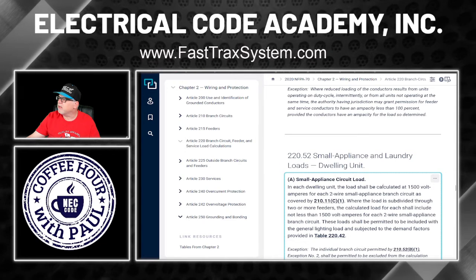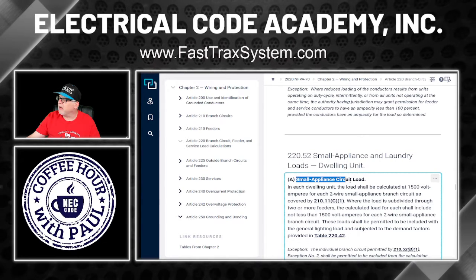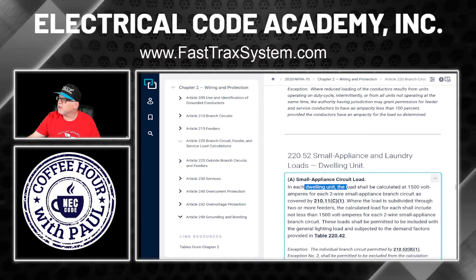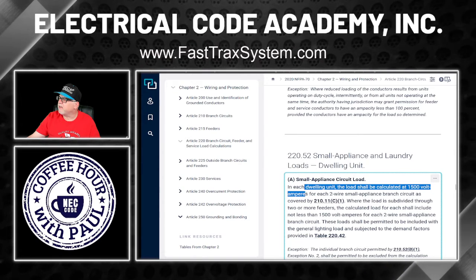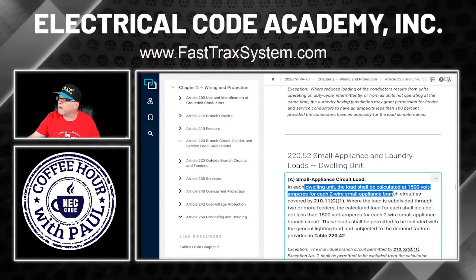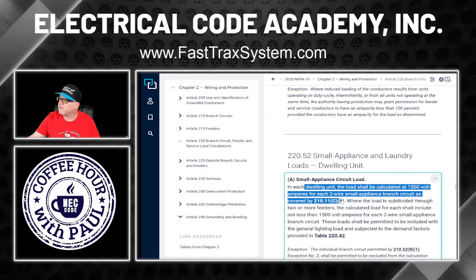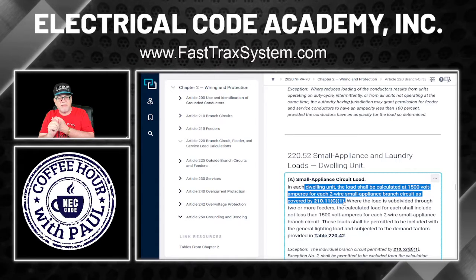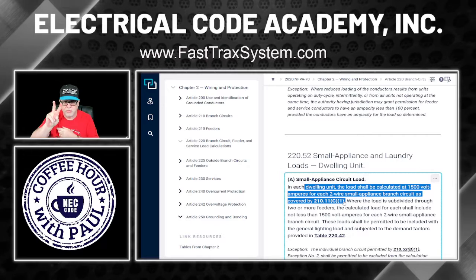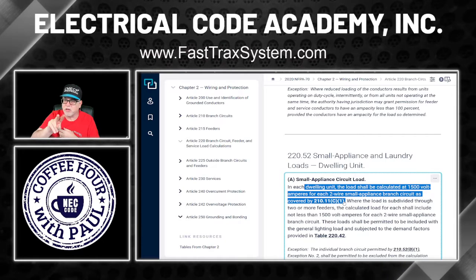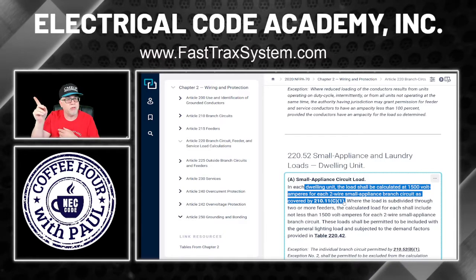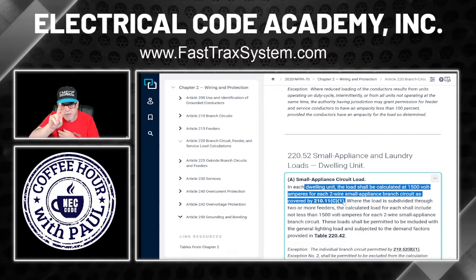So in this case, here we see what it says. For each dwelling unit, for the small appliance, the load shall be calculated at 1500 VA for each 2-wire small appliance branch circuit covered in 210.11(C)(1). Of course, if you know 210.11(C)(1), that's the one that requires a minimum of 2, right? That's in branch circuits, it tells you the number. You've got a minimum of 2. Could you have more than 2? Absolutely, but you have to have a minimum of 2.